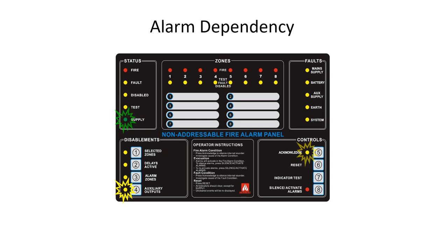Use the silence activate alarms button to step through the zone pairs for alarm dependency. Zones 1 and 2, zones 3 and 4, zones 5 and 6, etc. Check that the relevant yellow zone LEDs are on. When the zone pair is selected, confirm the selection by pressing the acknowledge button and check that the companion red fire LEDs are on. If required by the system design, repeat the process for additional zone pairs. To exit the alarm dependency configuration mode, simply press the auxiliary outputs button. The auxiliary outputs LED, the acknowledge LED, and the fire LEDs will all be off.